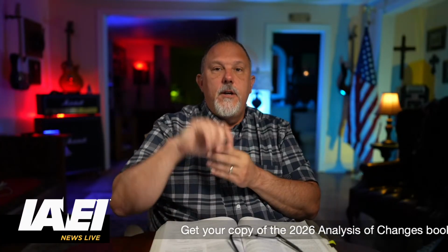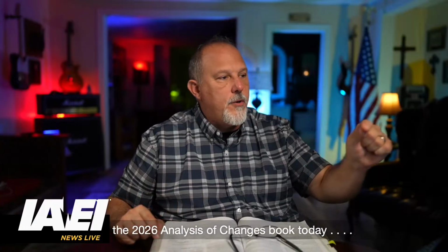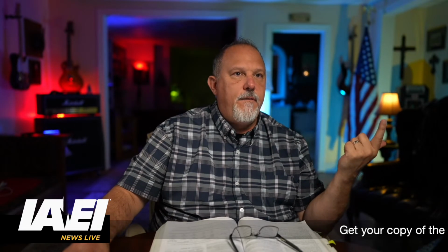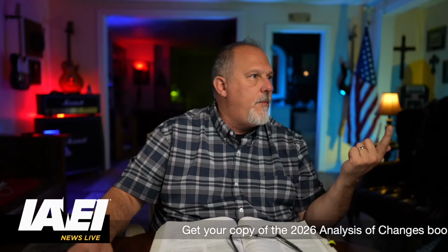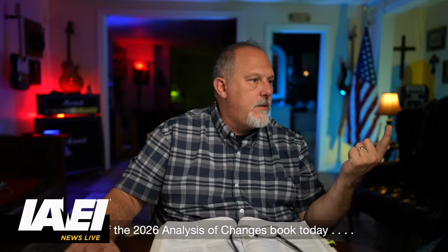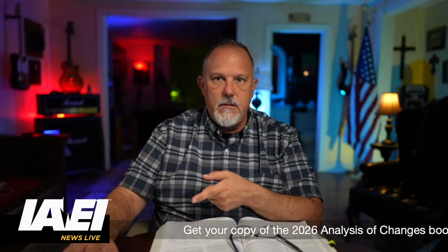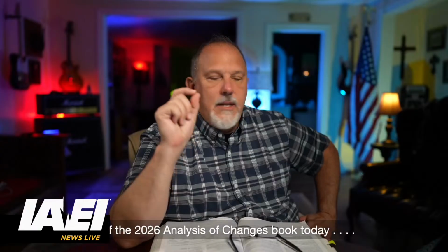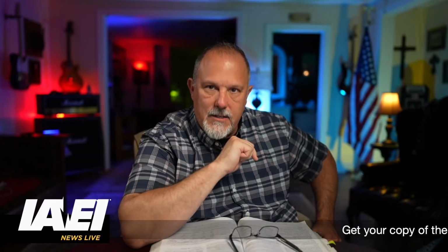So the difference of that is when I see the words standard rating, that means I'm going to Article 240. And I believe that would be 240.4, right, Dawn? Help me here. 6. 240.6. I always get 4 and 6 mixed up. 240.6 is titled Standard Ampere Ratings. So anytime you see the next higher standard ampere rating, that means you are governed by the table in 240.6.